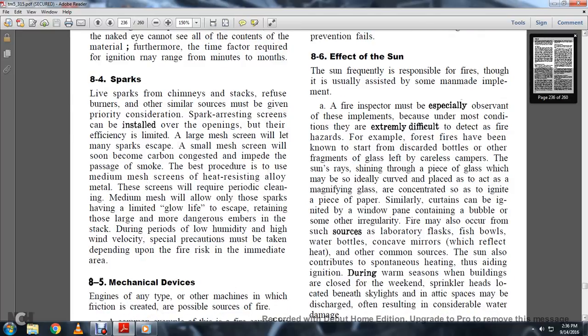8.4. Live sparks. Live sparks from chimney stacks, refuse burners, and other similar sources must be given proper priority consideration. Spark-arresting screens can be installed over the openings, but their efficiency is limited. A large mesh screen will let many of the sparks escape. A smaller mesh screen will soon become carbon-clogged and impede the passage of smoke. The best procedure is to use a medium mesh screen of heat-resisting alloy metal. The screen will require periodic cleaning.